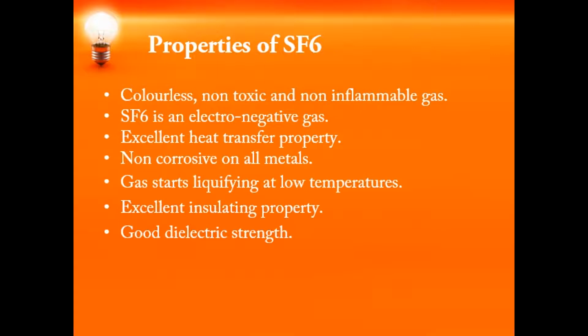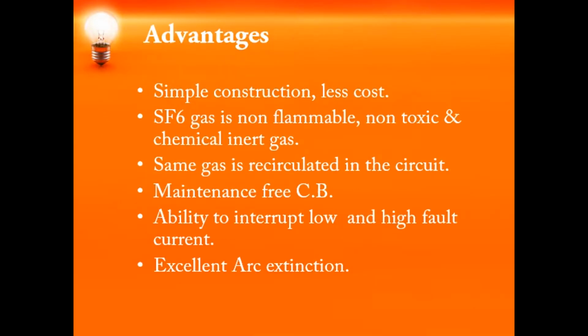The properties of SF6 are categorized as physical properties, chemical properties, and electrical properties. The advantages of using SF6 are, first, the construction is simple and costs less. Next, it is non-flammable, non-toxic, and a chemically inert gas. These circuit breakers have fewer arc interrupters when compared to other circuit breakers, and you need not replace the SF6 again and again. The same SF6 is recirculated in the circuit, and it is maintenance free. It can interrupt both high as well as low magnitudes of current, and it has an excellent arc quenching property.